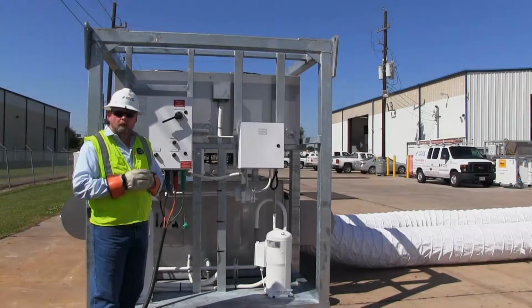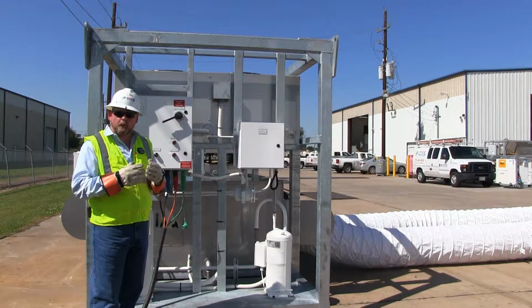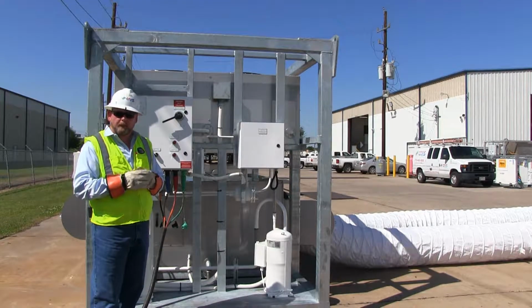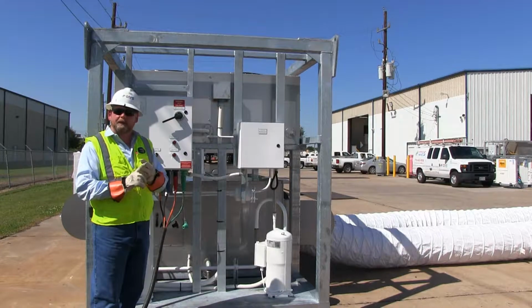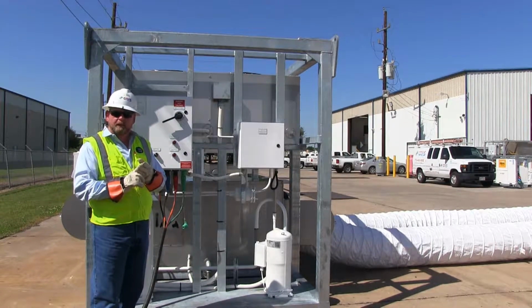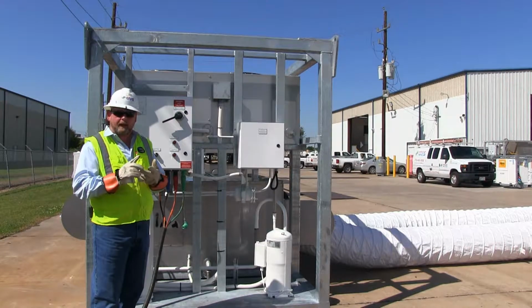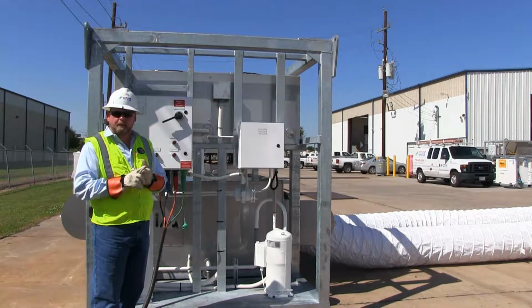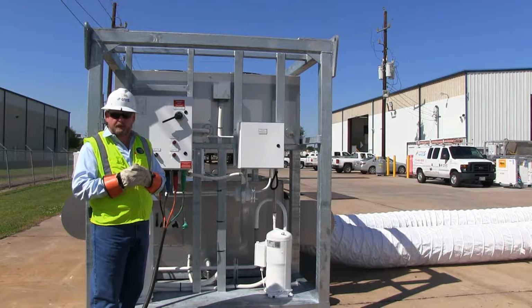Okay, to recap the setup of the 40-ton industrial air conditioner: we've set the unit level. We've connected the power. We've verified that our phase is correct. We've ducted in the intake and we've ducted the outlet, and we've primed our condensate trap. Now we're ready to operate the unit.